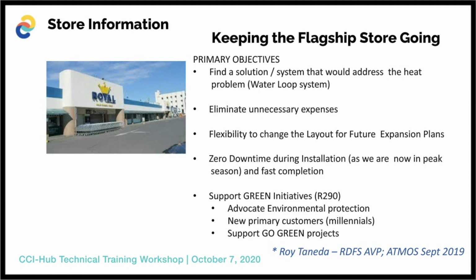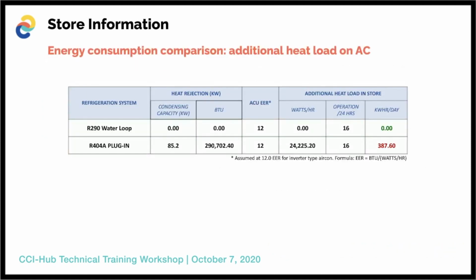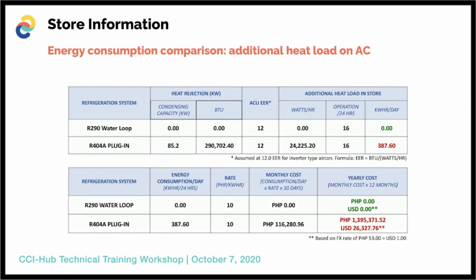If you look now at the next page, here you can see the benefits of a water loop system as opposed to that of a plug-in system, as there's no heat emitted into the store. Because of the high energy cost, this translates to approximately savings of about $25,000 a year in less cooling needed for the store due to the reduced amount of heat that is eliminated.